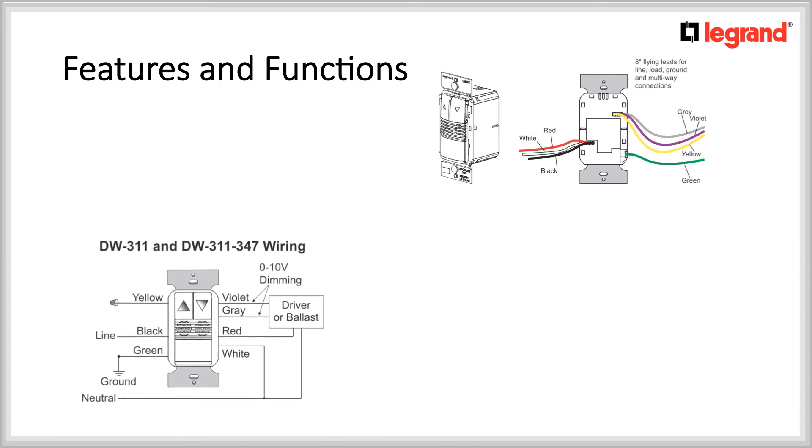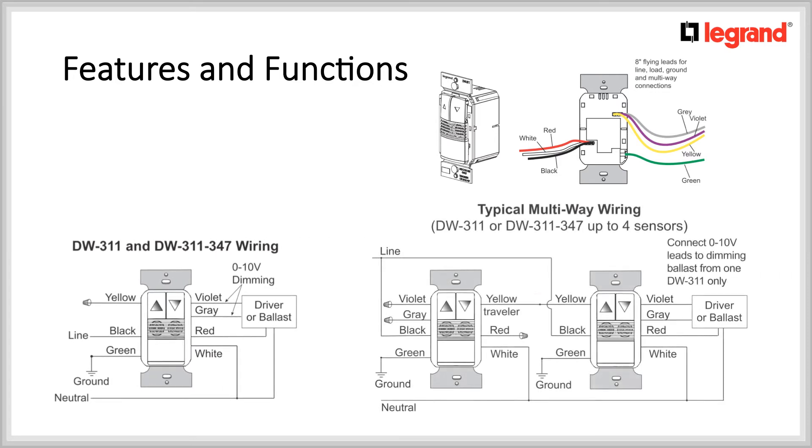Here's a quick view of the wiring diagram. The motion sensors come with colored wires which are easily identifiable. Note that for the DW-311, the neutral connection is optional. You will notice a yellow wire, but in a single pole application it isn't used. However, it is used for three-way applications. The good news is, these motion sensors can be used in multi-way applications.